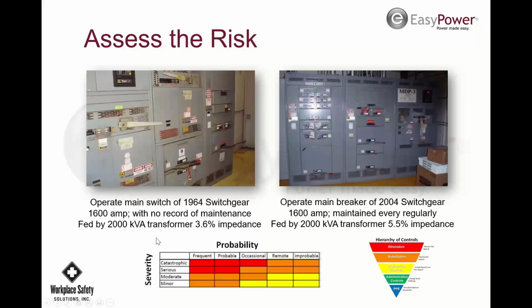So assessing the risk. You take a look at these two switchgears, and one of them is 1964. They're both 1600 amp. They're both 2000 kVA transformers, and they're both 480 volts. So they're essentially identical hazards, you would think, right? The first instinct for me and most people is the 1964 switchgear is going to be a little scarier than the 2004 switchgear. On the other hand, let's take a look at this a little bit deeper.